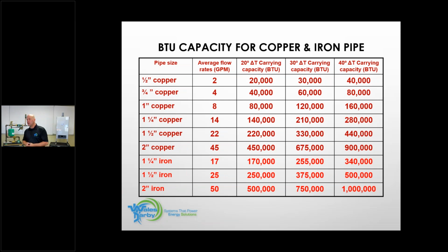So if I have a very large, let's say it's a school and I have multiple cast iron boilers or whatever boilers in there, I may want a larger delta T so I can reduce the size of my pipe. That's some of the reasoning for why we go to greater deltas than 20. Some good conversation popping up here.